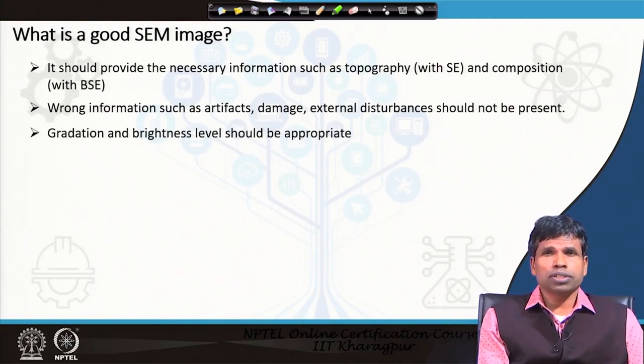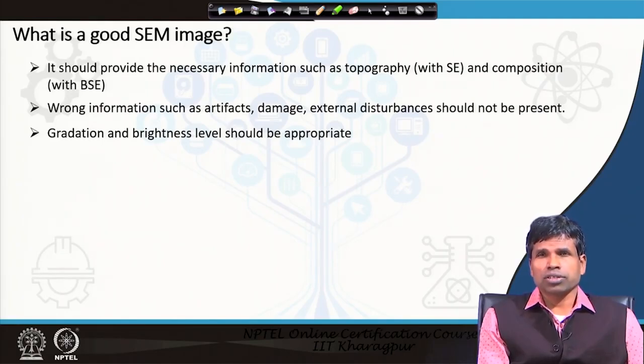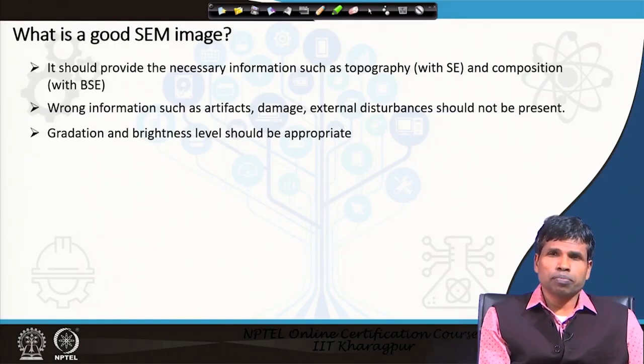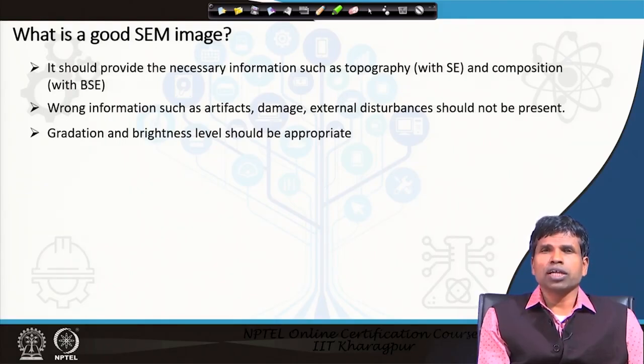Surface morphology is normally obtained with the secondary electron signal, because secondary electrons emerge from at or near the surface of the material. Therefore, they give us the best surface information with high resolution. On the other hand, backscattered electrons provide us the composition of the material, because the yield of backscattered electrons increases with increase in atomic number in the specimen.